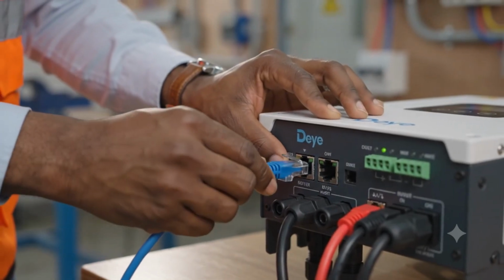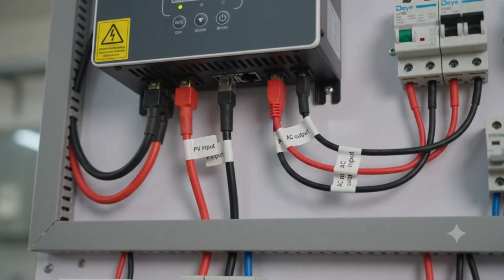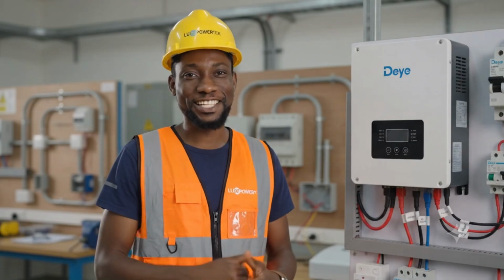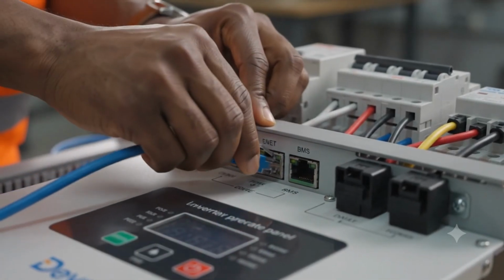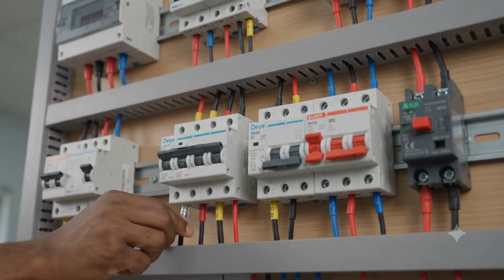We connect the PV, battery, and AC inputs along with the communication cable. Then we route the AC output and install isolators and breakers. Let's check them. We connect the communication cable between the inverter and lithium battery, and also install AC breakers and surge protection devices.